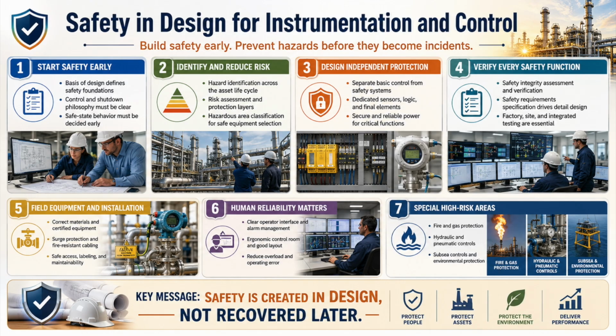Subsea control introduces a different risk profile. Human exposure may be lower, but environmental and financial consequences can be enormous. Hydraulic and electro-hydraulic systems require correct sizing, material compatibility, pressure containment, response analysis, voltage analysis, communications integrity, redundancy, spare hydraulic paths, and interfaces that divers or remotely operated vehicles can connect and disconnect reliably. Umbilicals, flying leads, subsea control units, accumulators, valves, electrical conductors, hydraulic tubes, and connectors must be designed as one dynamic system, not as isolated purchased items.